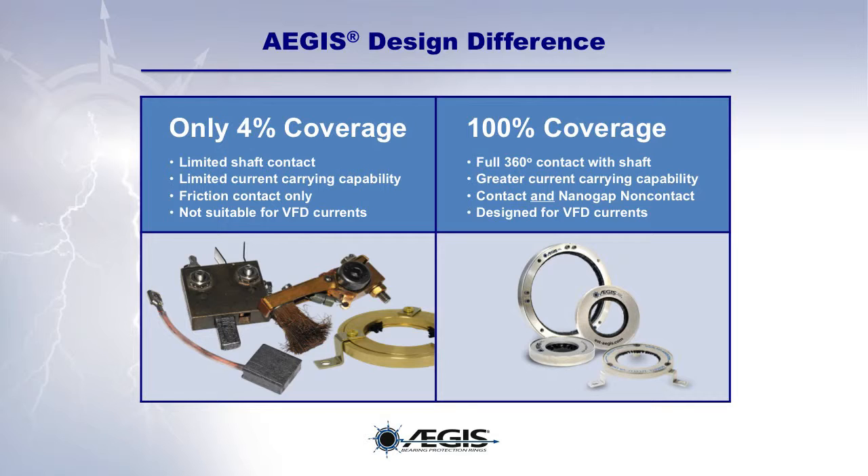Consequently, they are effective even in the presence of dirt, grease, oil, or other contaminants. And while other technologies are not suitable for use with VFD-induced shaft currents, AEGIS rings are designed to provide superior bearing protection for such VFD currents.